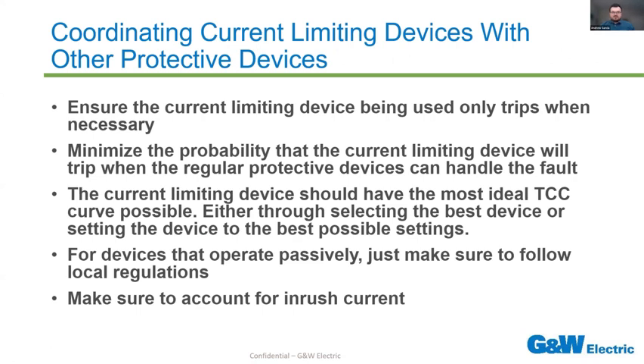So how do you coordinate these current limiting devices with other protective devices in your system? You want to ensure that these devices are only tripping and being used when absolutely necessary. AKA, you want to minimize the probability that these devices will trip when your regular protective devices in your system can handle the fault. Just increase your overall system reliability. So you want to make sure that when you're selecting these devices in the scope of your project, they have the most ideal TCC curve possible, either through modifying those device settings or just overall selecting whatever device, like the fuse, with the most ideal TCC curve. And if you are using a device that operates passively like a reactor, just make sure to follow whatever pertinent regulations there are. And once again, very important, make sure to account for inrush current.